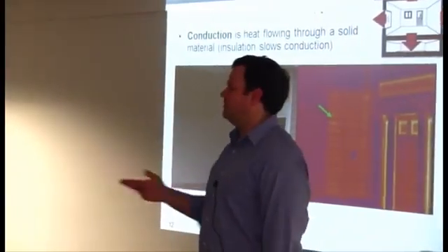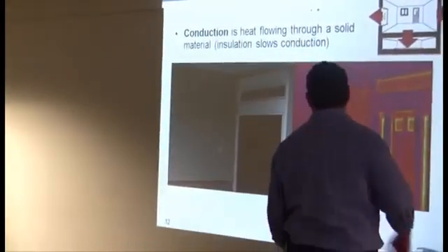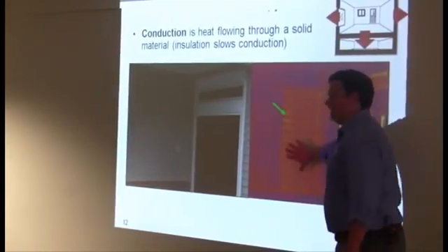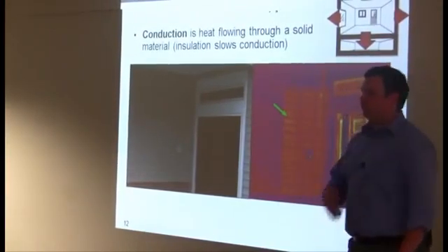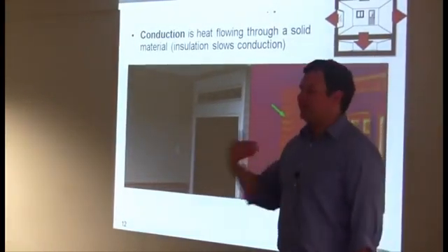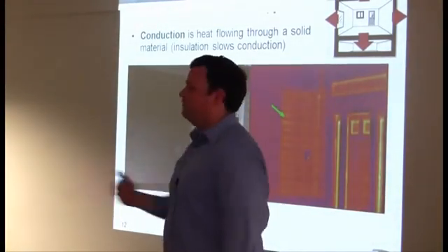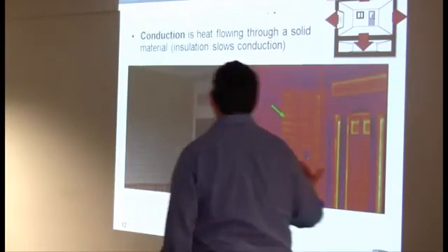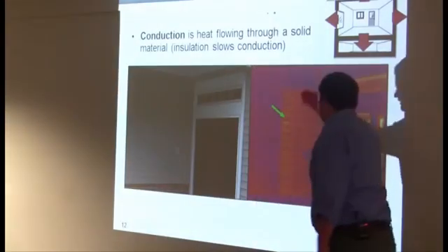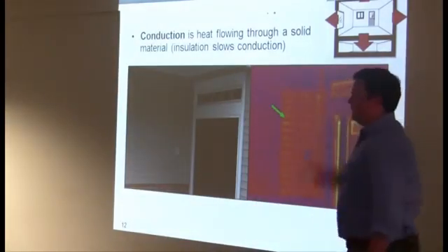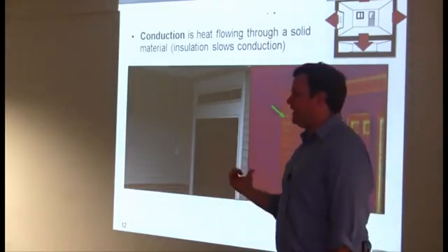I heard no insulation, right? So there is very little resistance to conductivity in this part of the wall. And of course, as I said, heat's lazy. It wants to take the path of least resistance. So it's flowing through the least resistant part of the wall. There's really no better insulation going on here than we have up in the transom window. So any idea why this might have happened?